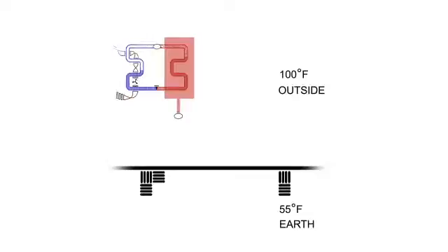In the summertime condition, the compressor reverses direction and the inside coil cools the recirculated air. Now we are in the opposite predicament, with the same energy-intensive result. The outside coil doesn't want to condense in 100-degree heat. It wants to evaporate. It's hot. So we replace the hot air with the mild 55-degree water, cooled by a water loop moving through the ground.